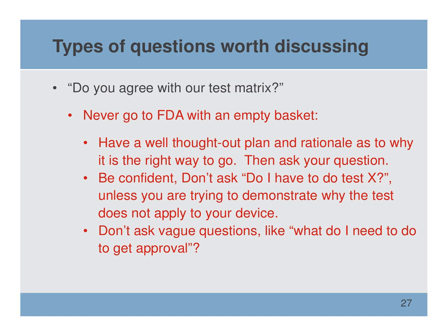If you've already done some tests, do not include the results of those tests in the pre-IDE or the pre-sub. Their job is not to review your test data and say it's okay. They're not here to bless your results. They're actually going to wonder, well, why are you sending this if you've already done it? So what we've done many times when faced with that situation is just say, look, tell them what the test is, but don't tell them about the results, because again, what you're trying to do is persuade FDA that this is the right testing to do. And again, just don't ask them vague questions like, what do I need to get approval? You really should have that figured out and then ask them to respond to your ideas.